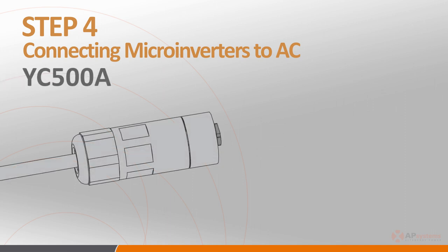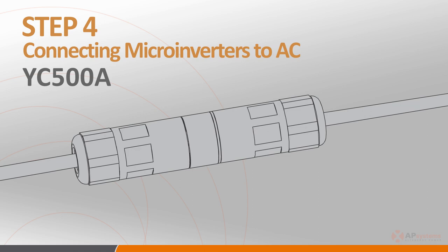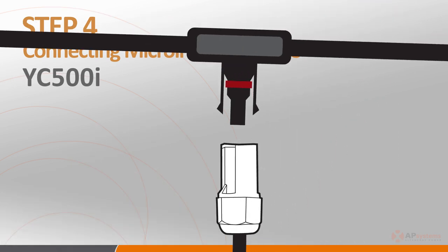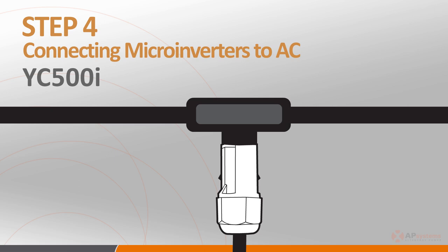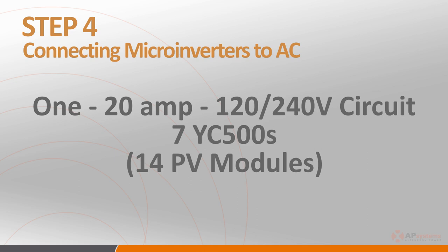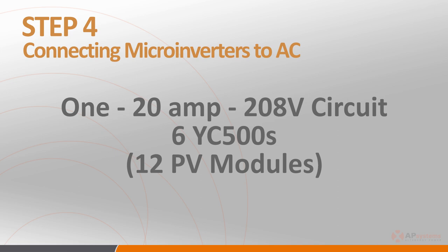Plug the female AC connector of the first inverter to the male connector of the next one, and so on, twisting the locking tab until you hear an audible click. For the YC500I, plug the AC female connector from the microinverter into the male connector on the trunk cable. When doing so, remember the branch inverter limits: the maximum number of units per 120-240 volt 20 amp circuit is 7, or a total of 14 PV modules, and the maximum number of units per a 208 volt 20 amp circuit is 6, or a total of 12 PV modules.